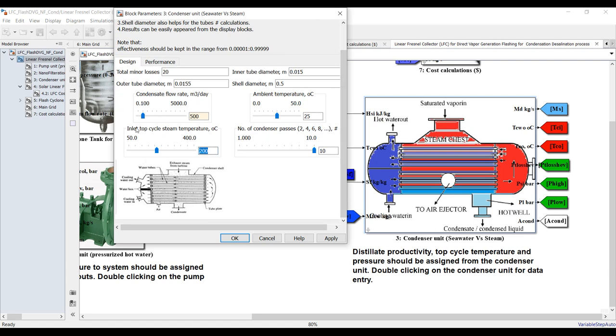This is only the top steam temperature because this comes from the flashing tank. What is your target top brine temperature? For safety reasons, I would recommend 120 degrees Celsius — no more than this. Surely this will affect drainage fraction, but you can change this and study the effect.